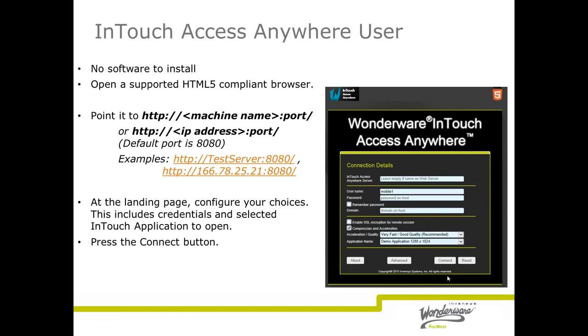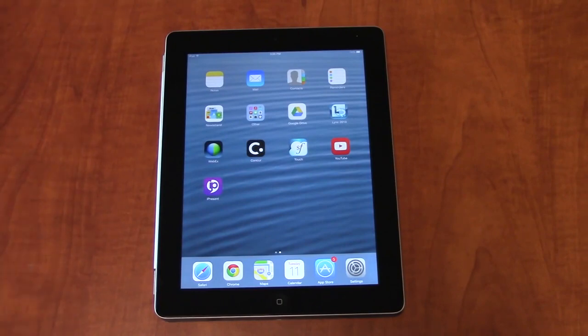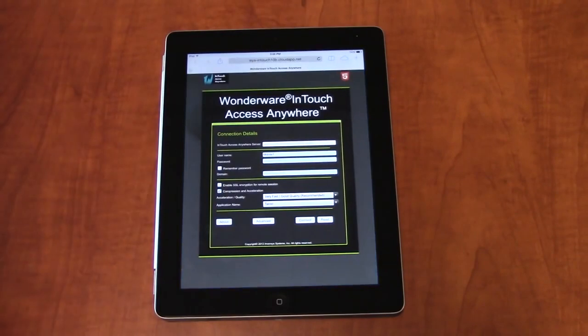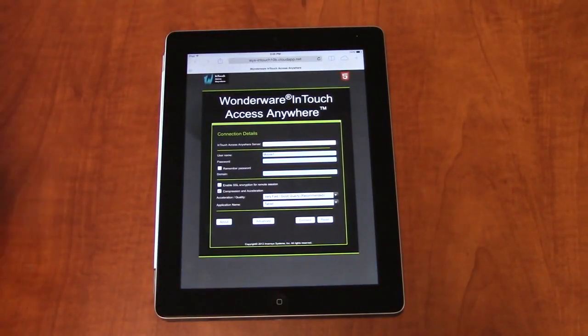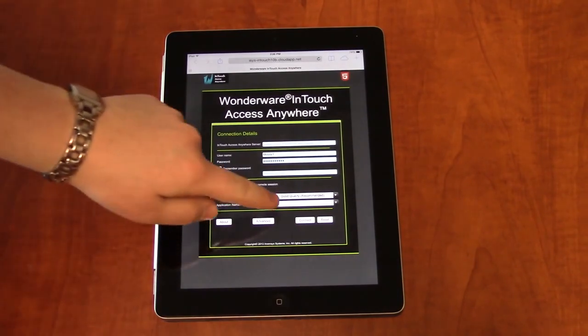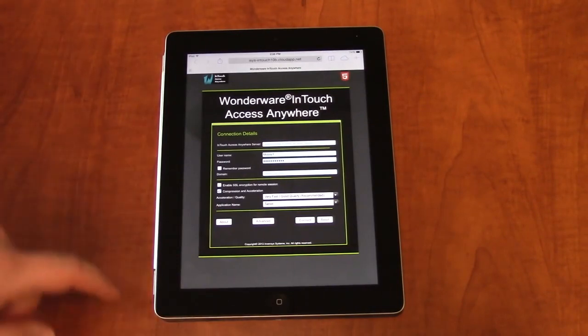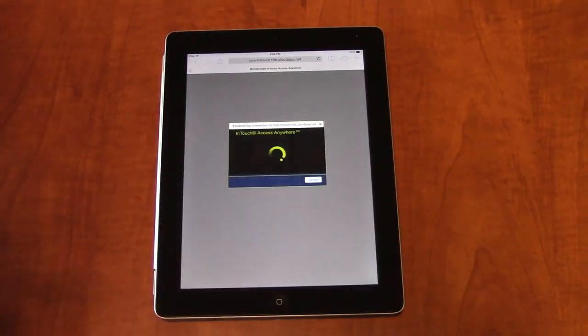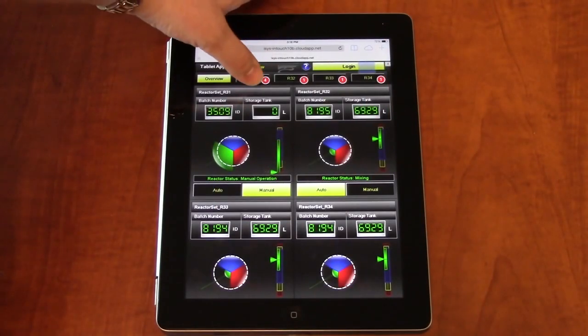Now we'll look at an example of connecting to InTouch Access Anywhere via an iPad. To use InTouch Access Anywhere, we'll simply open our iPad and start our browser. Here we've gone to the demo site, but this is where you would put in the HTTP address, including your machine name and the port 8080. This launches the login screen. Now we'll enter our username and password. From this menu is also where we select the application that we're going to remotely access. Here we only have one option. Then all we have to do is hit connect to get to our InTouch application.